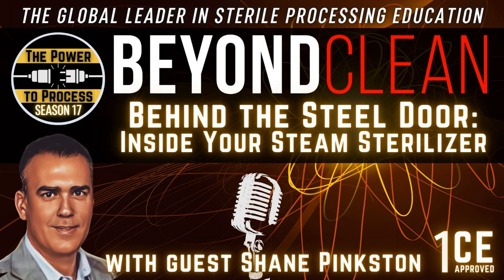I think we've seen the trend start — it probably began seven to ten years ago. Clean steam has become a hot topic, because of all the staining issues and the ability to control your own steam with an internal generator. A more clean product delivers a better clinical outcome. I think we're going to see more prevalence in that arena, whether it's internal generators on sterilizers or some external type of generator capable of producing better quality steam separate from the facility steam.